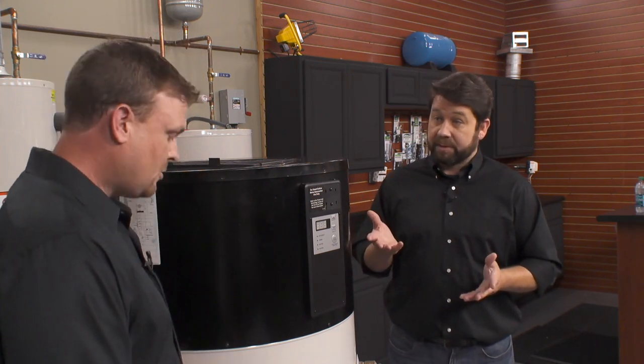The key to the efficiency is having heat in the air around it, so we want enough volume of air. We recommend 700 cubic feet as a minimum. We can go down to 128 cubic feet if we make accommodations like a louvered door, exchanging air with another part of the home so we can provide that heat into the air. So I've got to have enough air for the heat pump to work properly.